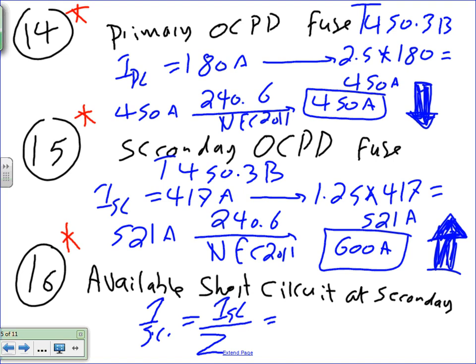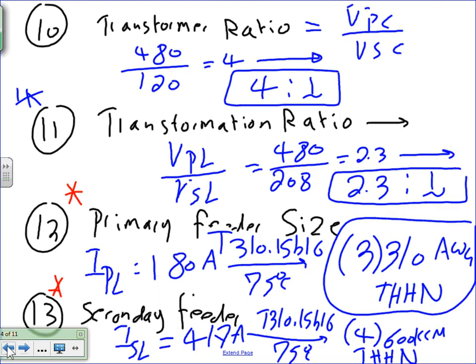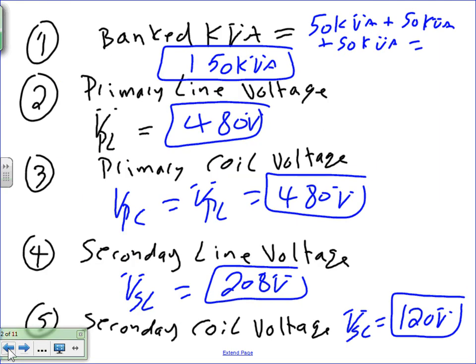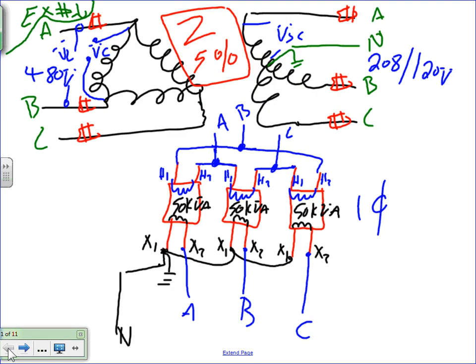I emphasize this a lot in the industrial because now you guys will be doing short circuit analysis for me as we move forward. When we size the short circuit, it is always on the secondary of the transformer, guys. If you want to calculate it for a transformer, this is the assumption: there's an unlimited amount of current that Excel can pump into your building. Unless you know otherwise, you have an unlimited amount of short circuit coming from Excel or any power company.